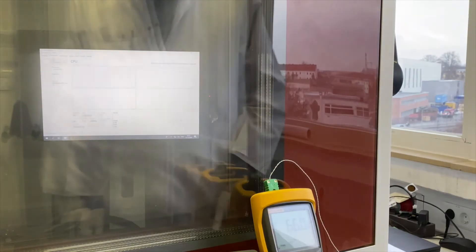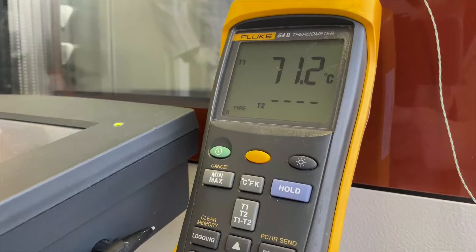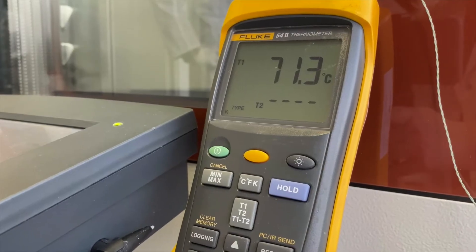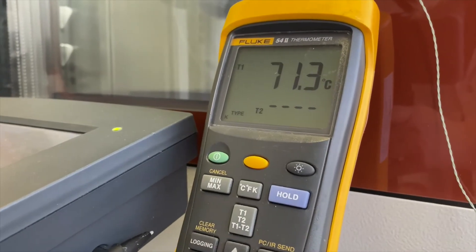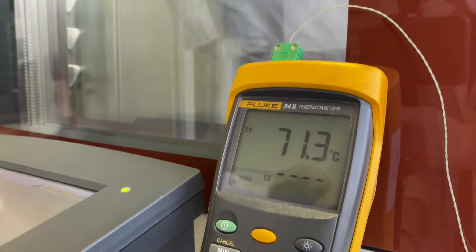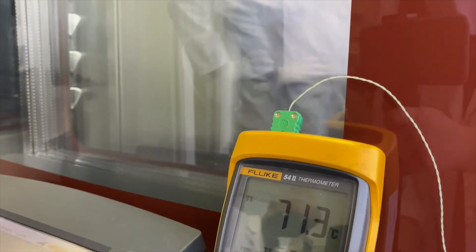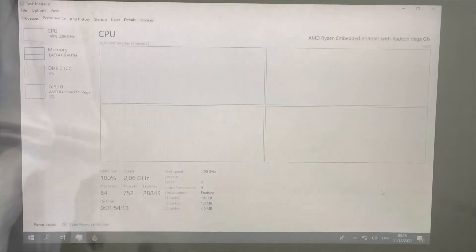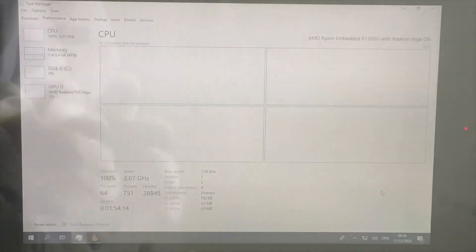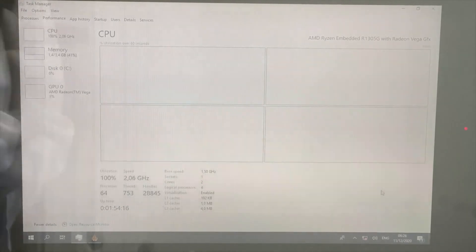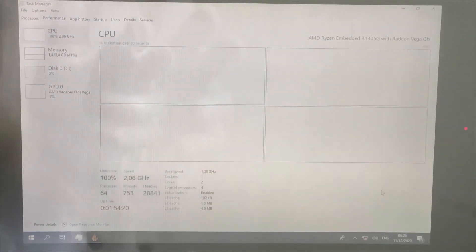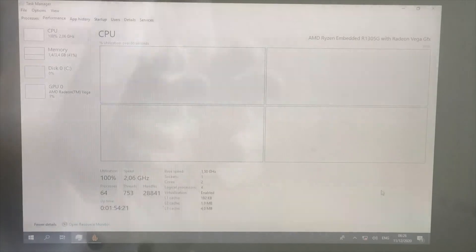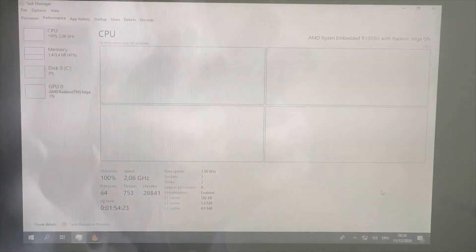But let's see what happens. Now you can see that ambient air temperature around the units is 70 degrees C. The processor remains 100% utilized. The nominal frequency remains 1.5 gigahertz and actual frequency is jumping up to 2 gigahertz. You get the full performance at 70 degrees Celsius with no active airflow.